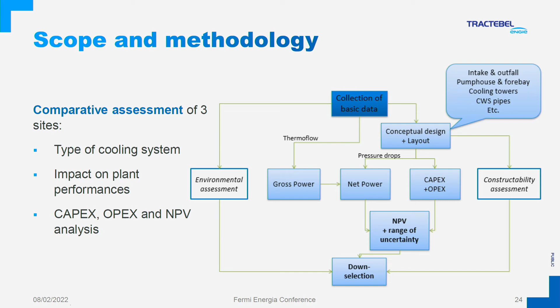In the cooling studies, the purpose was to compare different cooling options associated with the sites. A site away from the sea can only use closed-loop cooling, which affects the extent of the piping lines needed to connect to the water intake, the plant, and the outfall. That all has an impact on plant performance, and the main features of the cooling system have associated capex and opex. So we compared all those different cases through an NPV analysis.